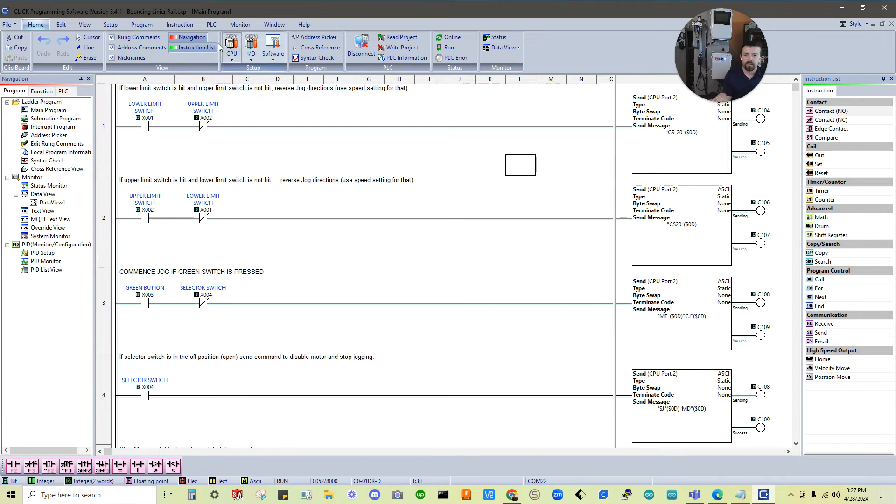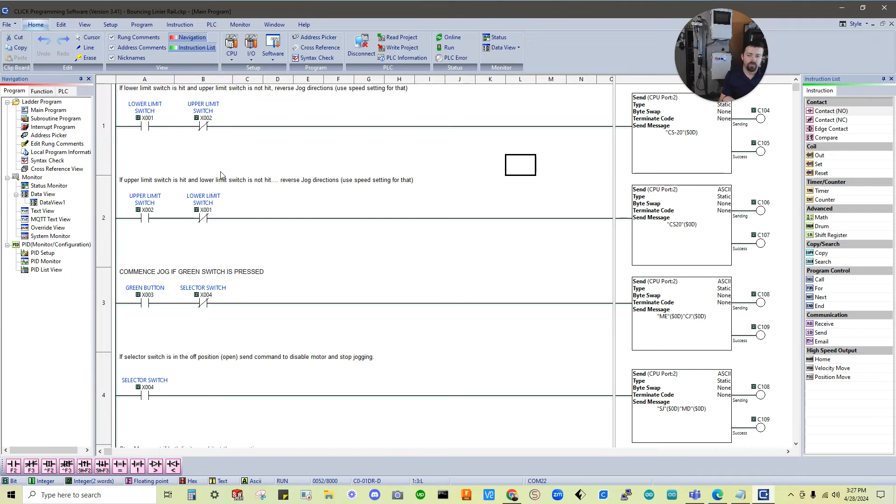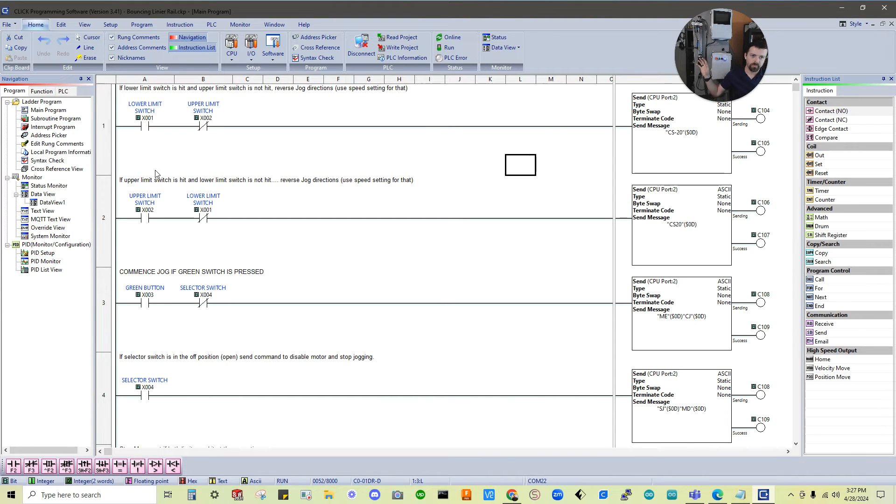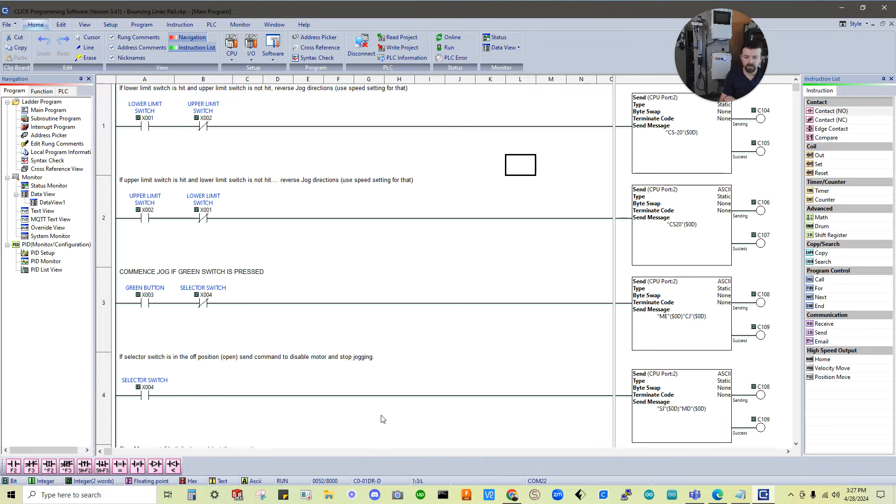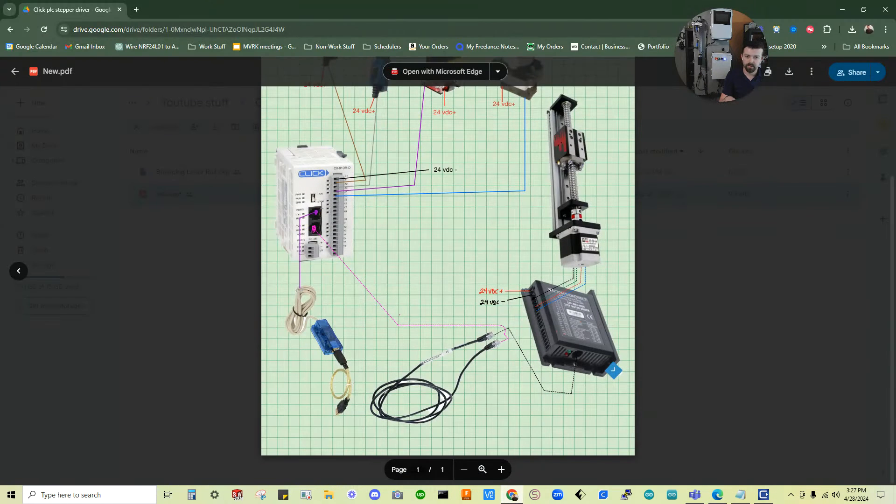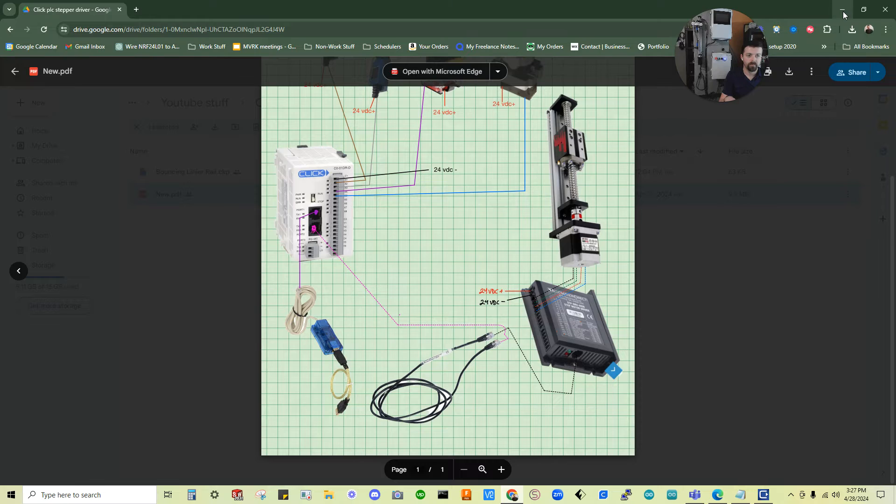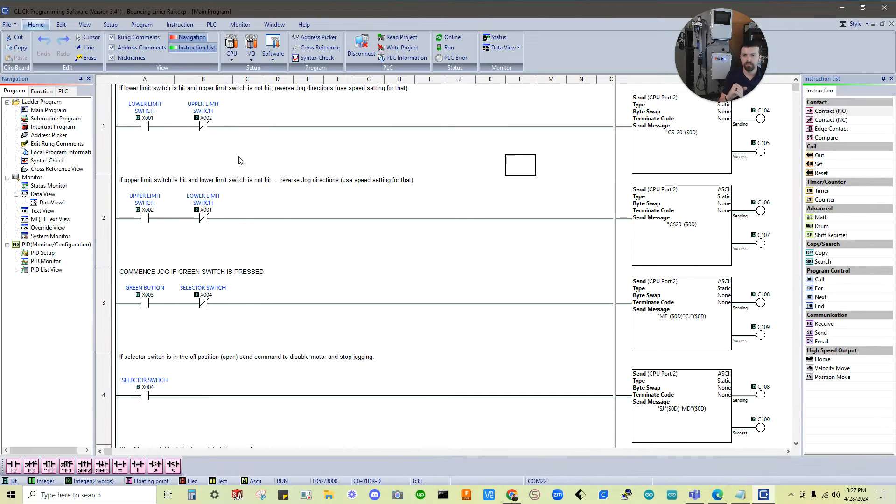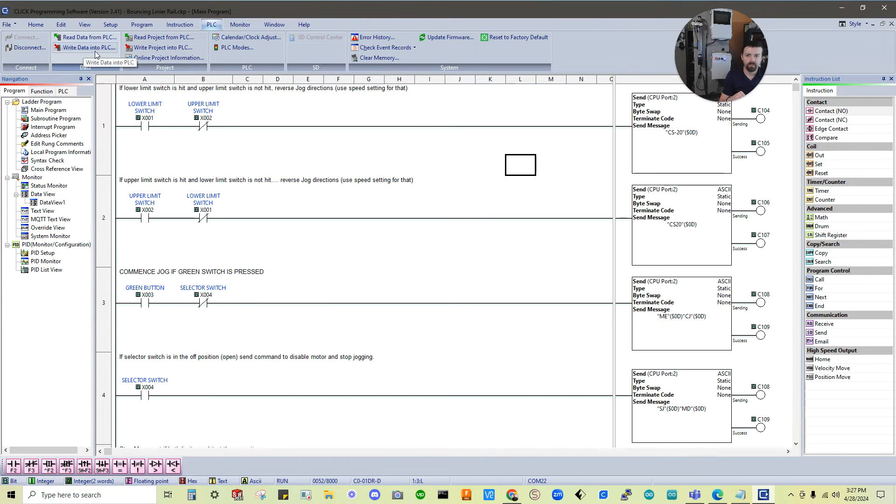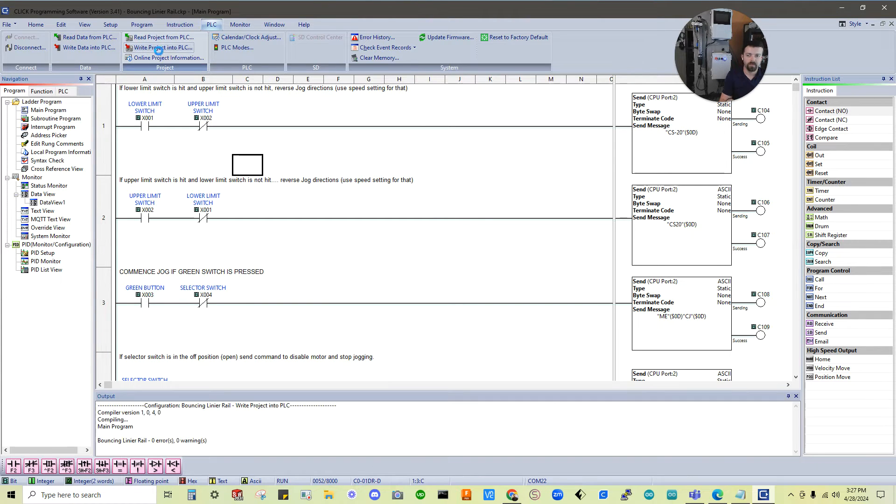So we've now attached, or brought in this program, but it's not in the PLC yet. So we need to write this project to the PLC. But again, make sure everything's safe, nothing's about to be hit, or if anything moves safe. One of the best ways to do that is put it into stop mode, or not have things connected at first, until you've done the basic setup. But we can go to the PLC tab, and then write project into PLC. Not write data into PLC, write project into PLC.